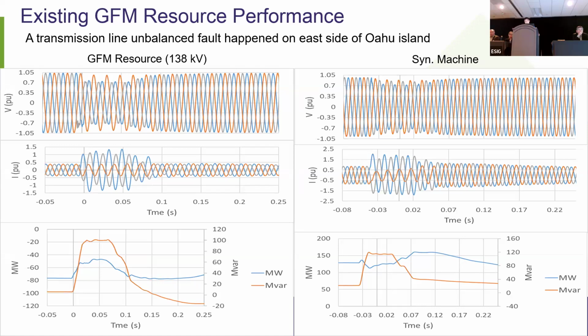When we look at the power measurements, we can see during the fault both resources provide very strong support, also including the recovery stage and the post-recovery stage. For the grid forming resource, the whole performance is very, very stable. We do not have monitors inside of plants, and we don't know what's really going on inside the plant. So this is what we can share so far. We need to talk with the developer and OEM if we really want to look inside a plant.